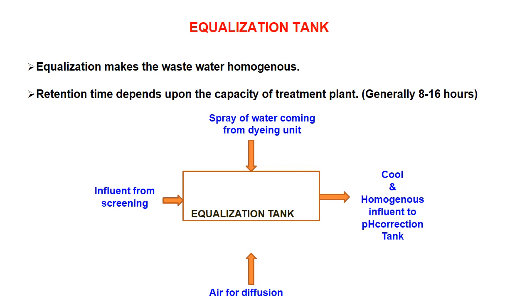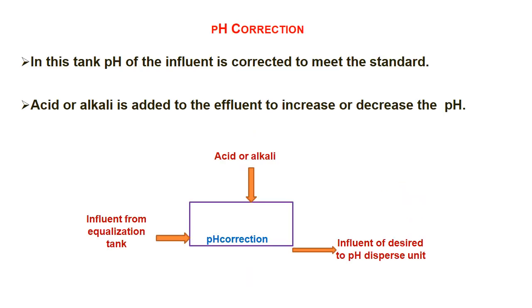Here we can see the equalization tank — it makes the wastewater homogeneous, and retention time depends upon the capacity of the treatment plant, typically 8 to 16 hours. The influent comes after screening into this tank, spray of water from the dyeing unit is added, air is infused, and everything is mixed together to get a cool and homogeneous influent with adjusted pH, which then goes to the pH correction tank. In the pH correction tank, acid or alkali is added depending on the nature of the influent to decrease or increase the pH to meet the standard.